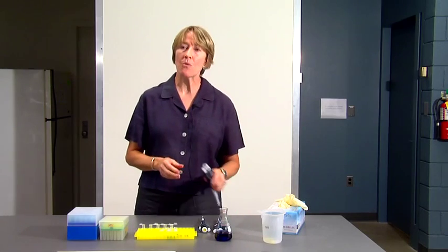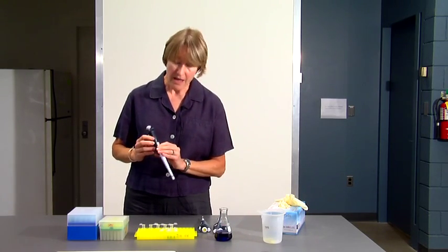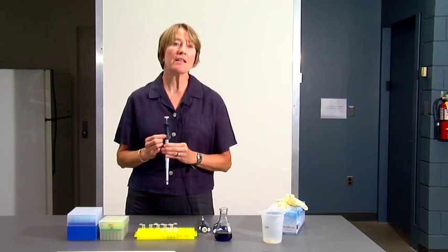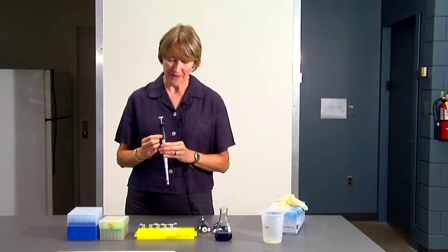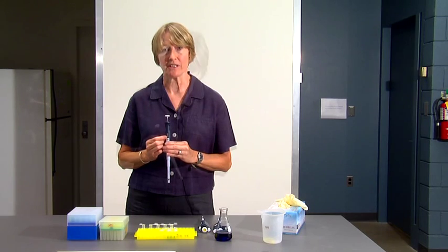Now let's look at the P1000. The P1000 also has three numbers, but notice that the top number is in red. So that's an alert signal. The top number is not 100s, it's thousands. So 100 is not 100 microliters, it's 1000 microliters.